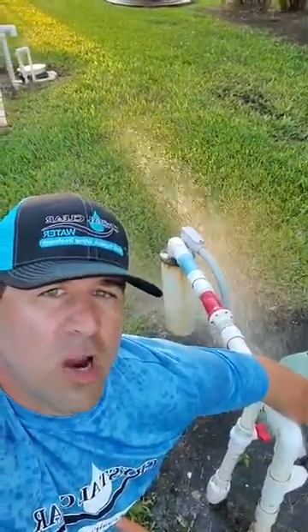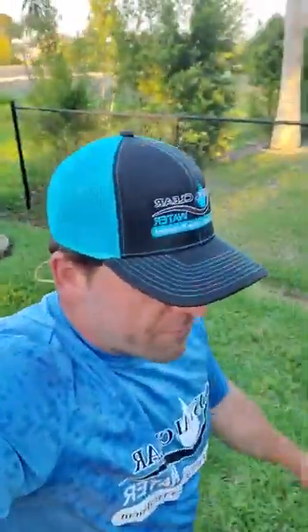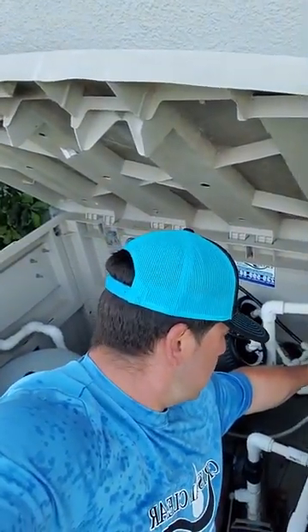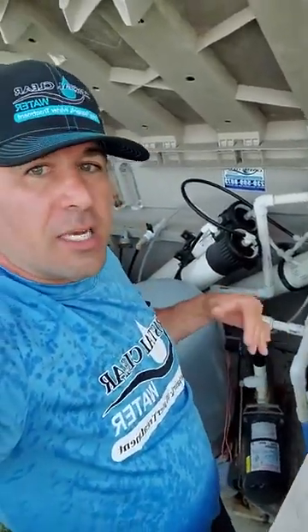If you have an aerator or a whole house RO, you're not going to notice this happen because you're basically going to run out of water before you realize there's a problem. So if you hear that noise, make sure you call us because you don't want your booster pump to go bad either. That noise is your booster pump starving for water, which could mean your filter housing has a plugged filter or you're struggling for water. Either way, it's a problem — it'll make your pump go bad. And if you're getting sand from your well into your filter housing, it'll plug it up and do the same thing.